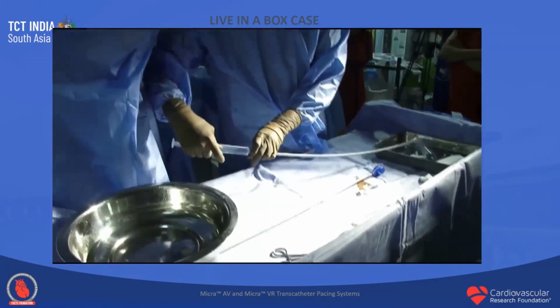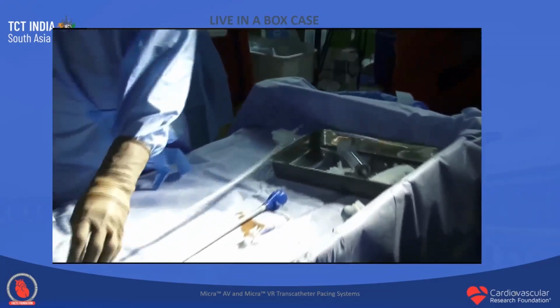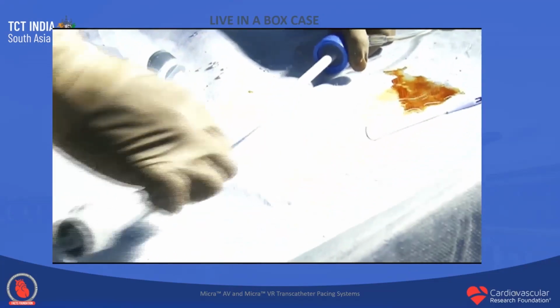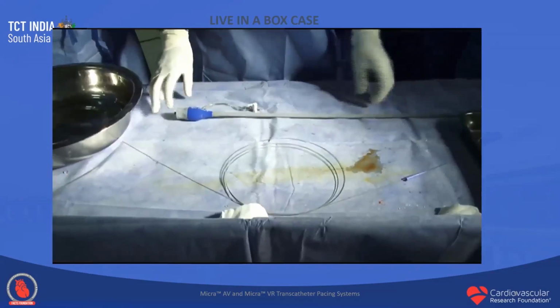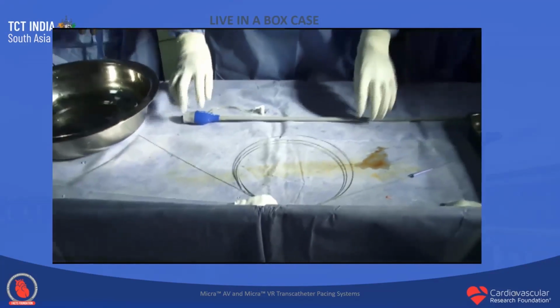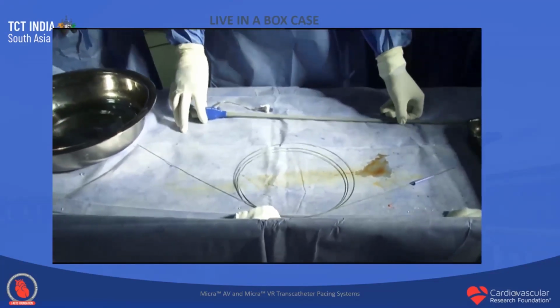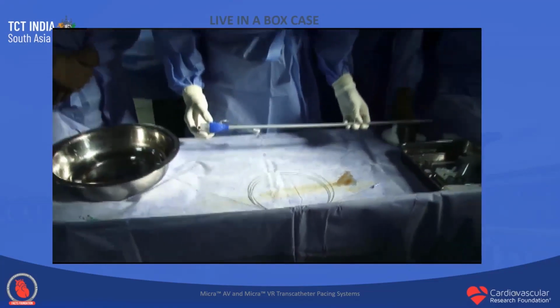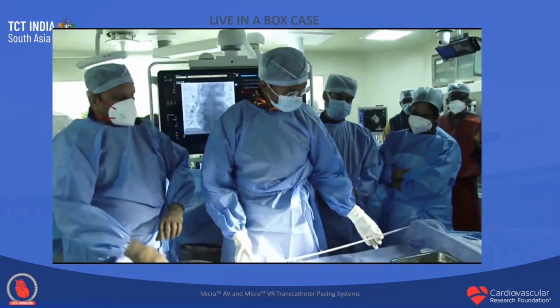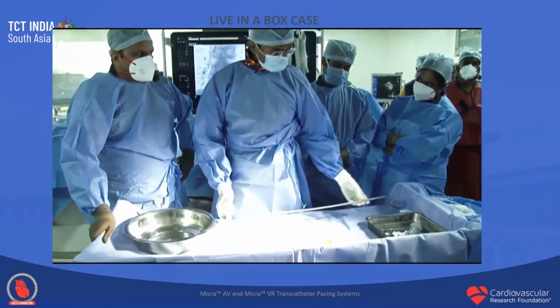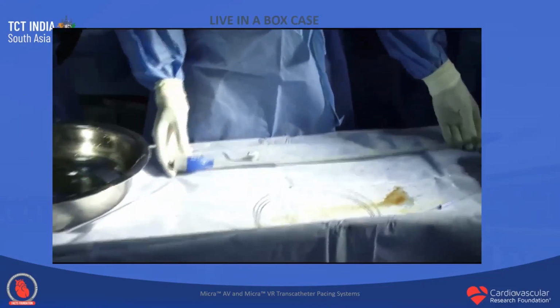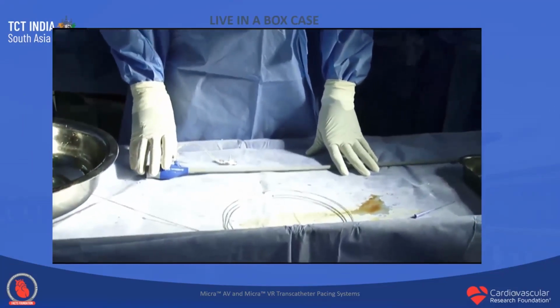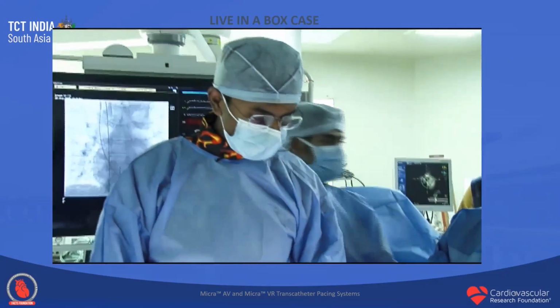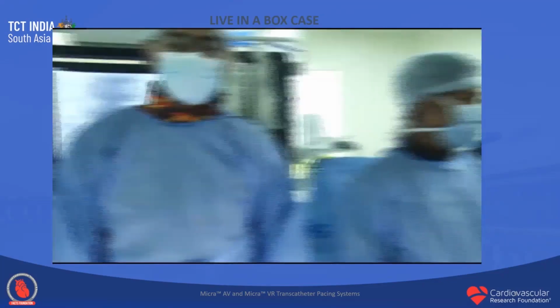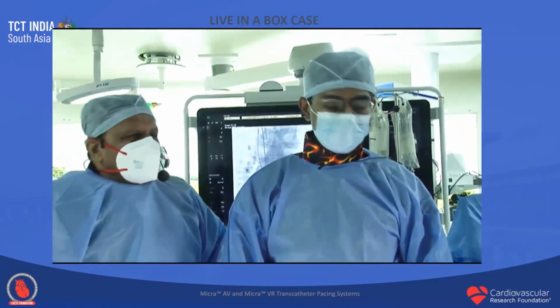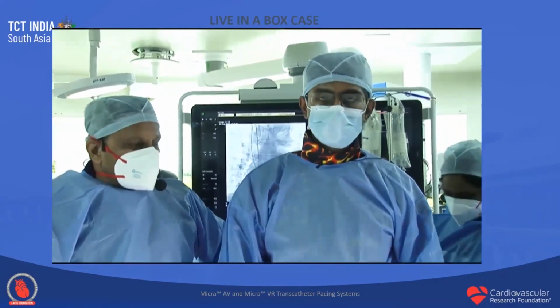So this kit comes with the sheath and wire as well as the Micra system. So this all comes as one package. The sheath is already prepared and flushed. The wire is there. We can open the Micra. So this is the Medtronic sheath. The outer diameter is 27 French and the inner diameter is 23 French. This is a 56 centimeter sheath, through which we will be taking the MDS system, the Micra delivery catheter system, for which we would first need to put a stiff Amplatz super stiff wire into the right side of the heart, and then we will position this sheath within the right atrium.